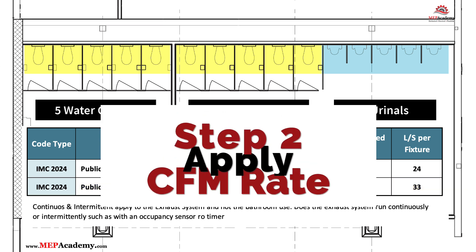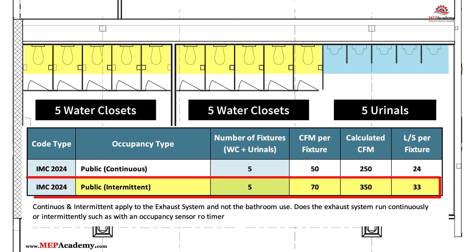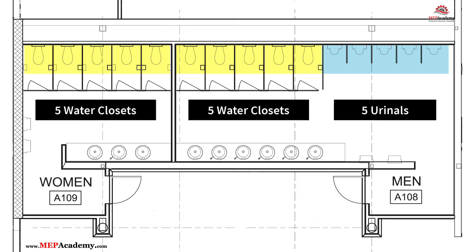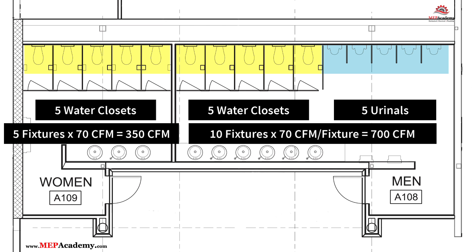Step 2: Apply the exhaust rate. Using IMC 2024 for intermittent operation gives us 70 CFM per fixture. Step 3: Calculate the total airflow. For the men's restroom, 10 fixtures × 70 CFM = 700 CFM required. For the women's restroom, 5 fixtures × 70 CFM = 350 CFM required.